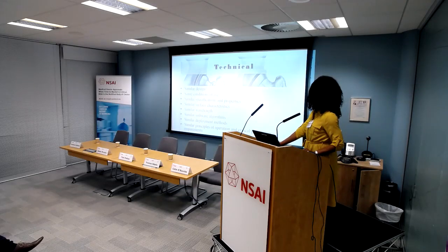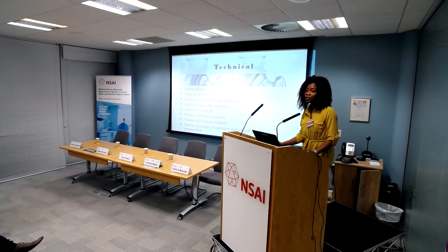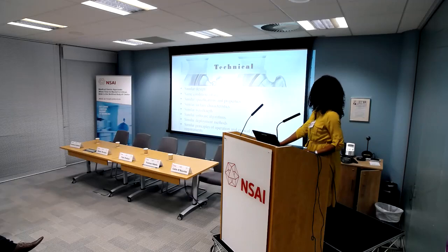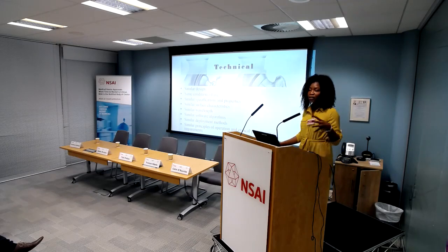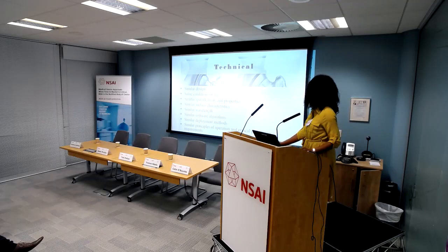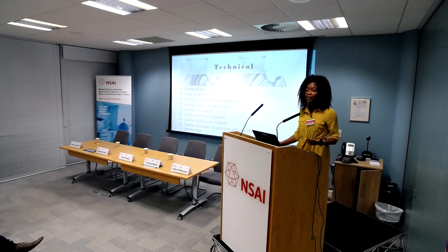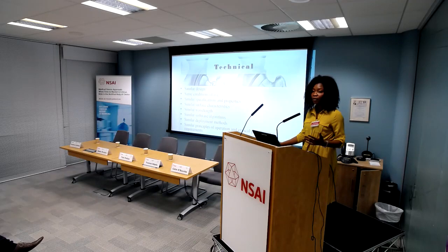From a technical perspective, you should ensure that your device and the predicate device have a similar design, the same conditions of use, similar specs and properties, and similar surface characteristics. If you're using a specific coating, the predicate device should use the same coating, so there should be no difference in the surface characteristics. If it's software, it should be the same software algorithm and the same deployment technique. In a case where you have a stent as your device, the predicate device should have the same deployment technique as your own stent.